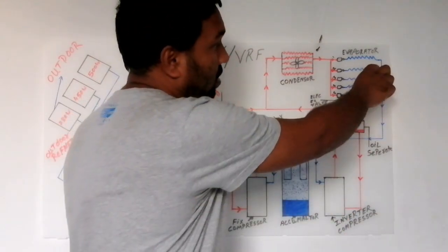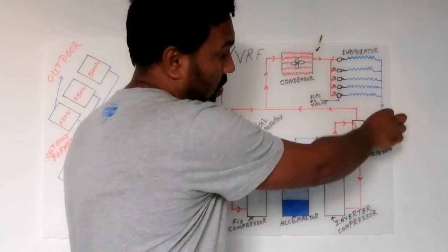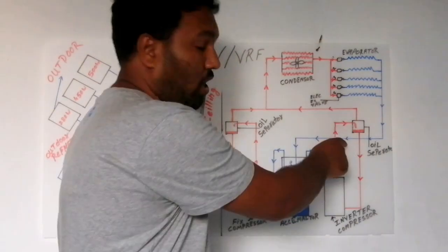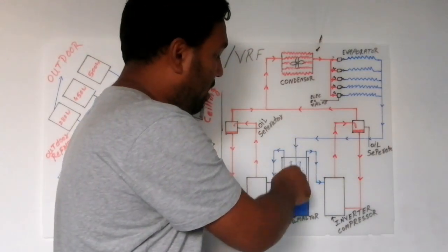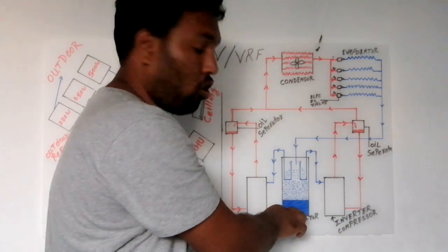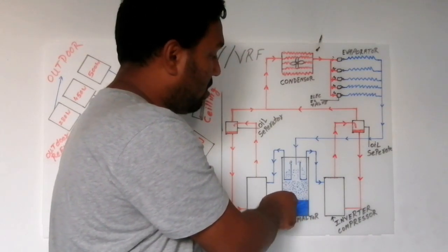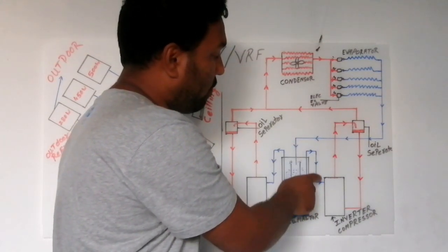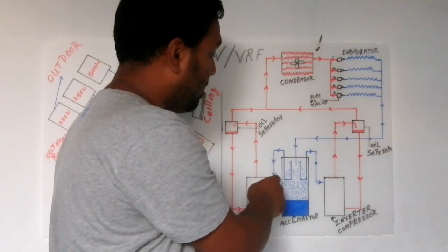First of all, we will start from the accumulator. Whatever liquid refrigerant comes from the evaporator comes to the accumulator. Whatever liquid is present in the refrigerant gets settled at the bottom of the accumulator and gets vaporized, then it gets sucked in by each of the compressors, inverter as well as fixed.